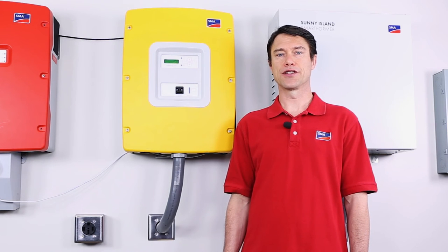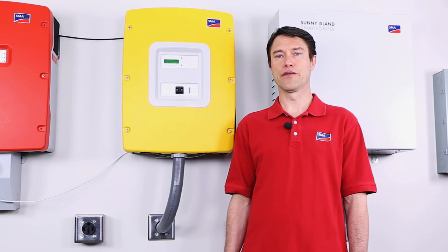Commissioning a Sunny Island system with a new battery that uses an external BMS is a simple procedure. Before you begin, however, ensure that the Sunny Island system has the most current version of the firmware installed on it. If you need help installing firmware on the Sunny Island system, please consult the Sunny Island Firmware Update Tech Tip video on our YouTube channel by clicking the link below.